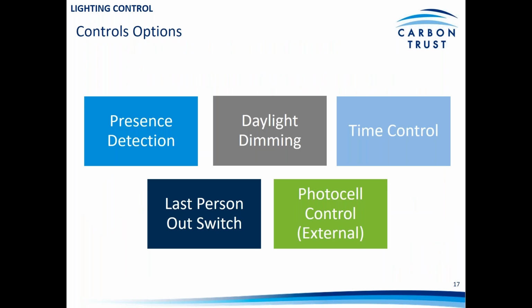So in terms of options, we've mentioned a few there already on lighting. Presence detection is widely used through the use of PIRs to detect motion and to switch off lighting unless somebody is in a space. Daylight dimming sensing too is useful, as too is simple time controls. Again, back to the similar example as we had in the heating section. You can set your lighting to switch off basically at the end of the working day, or after cleaners have gone home, and do that automatically to make sure that the lighting isn't left on.